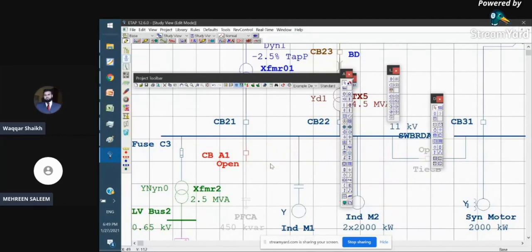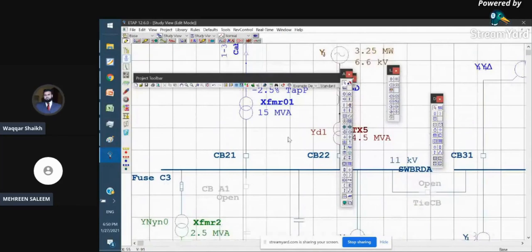If you go into the technical depth of this continuity check—even in ETAP's help documentation—you'll find that it doesn't mean connection correctness. It means that a given component, bus, or electrical equipment is connected to a swing source, directly or indirectly. A swing source is mandatory for running any type of study. If there is no swing source or swing bus in the network, the network cannot be energized.